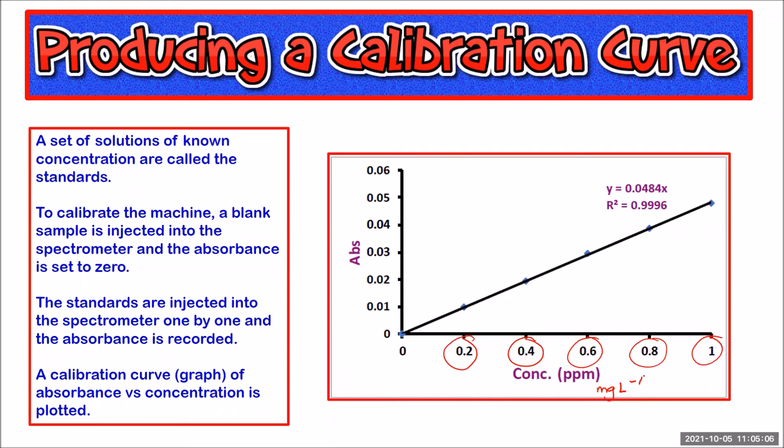To calibrate the machine, first of all you inject a blank sample and set the absorbance to zero so that you get your zero point. Then your standard solutions that you've made up, one by one they're injected into the spectrometer and their absorbance is recorded and we plot each of those absorbances to produce what's known as a calibration curve.